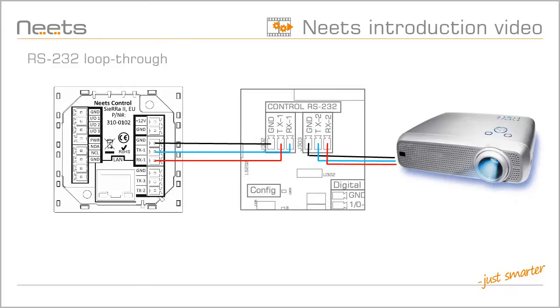But with the Switching Relay 4, you can use the RS-232 loop-through feature to connect the relay box without using an extra RS-232 port. Neets Switching Relay 4 is not limited by the baud rate, so each port can run at a separate baud rate and still be working.